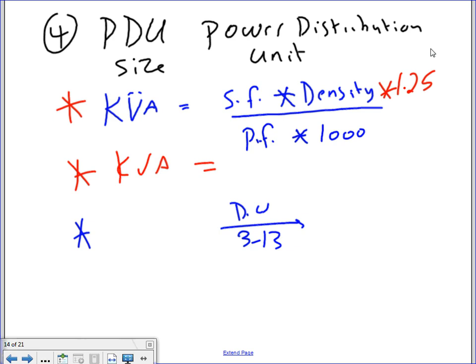For the PDUs, do me a favor. We're going to do the same calculation, guys. Change this one to loss factor, please. Loss factor here. Can you guys change this one to loss factor? And we're going to do the same identical calculation that we did. PDUs and UPS, same identical calculation, guys. So we're going to have number 4 here.